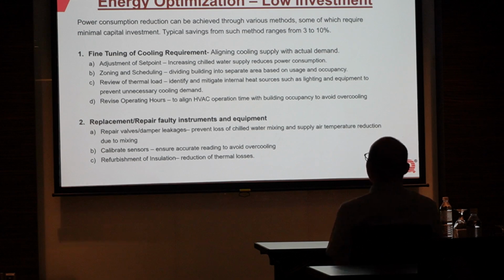A lot of the time, once the design is set - let's say we supply 7 degrees or 5 degrees chilled water - the facility team won't change the set point. They continue to operate even though it's cold in the space. But if you increase the chilled water supply temperature, the power saving is substantial. There's a rule of thumb: every 1 degree increase in chilled water temperature saves about 3% of chiller electricity consumption, and the chiller consumes the most in the chilled water system.